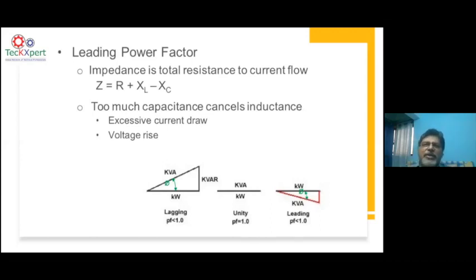For example, let's say you have a capacitor bank of 25 kVAr, 4 steps. Now, let us say the system requires 30 kVAr. What does the active harmonic filter do? It will bring in the 25 kVAr step first, and it will inject the remaining 5 kVAr. Now, assume the reactive power requirement has gone down to 20 kVAr. Then what does the active harmonic filter do? It will still maintain that 25 kVAr capacitor on the grid, and it will inject a lagging power factor, so that it brings it to 20 kVAr.